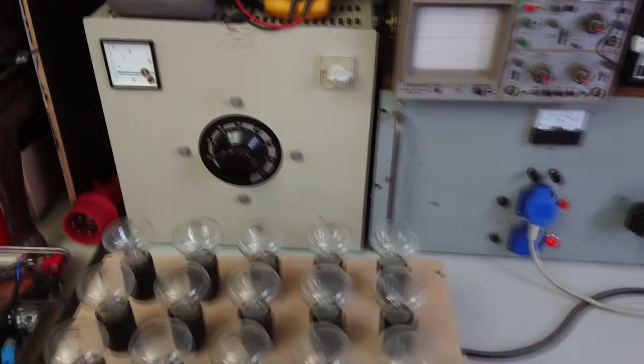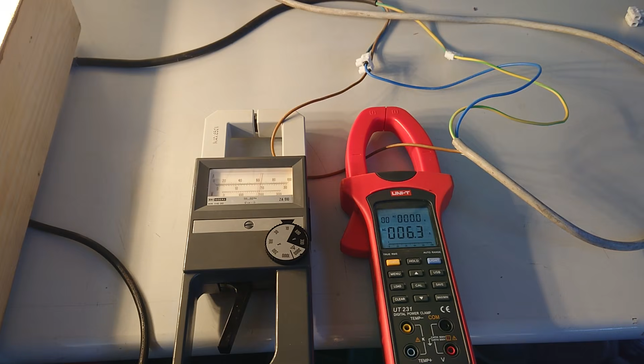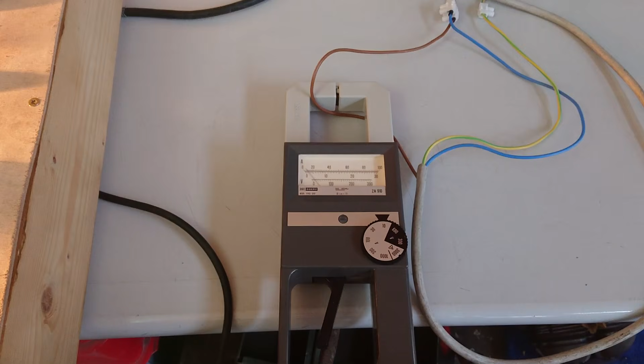I'm testing it with my light bulb dummy load. At this moment it's switched to its lowest setting, 10 amps. These clamp meters work by clamping them around one of the conductors to measure AC current. This older meter has a few advantages: it's much quicker than the digital meter, which wasn't able to measure some of the current bursts I saw. It needs no batteries and has a much higher current range, up to 3000 amps.